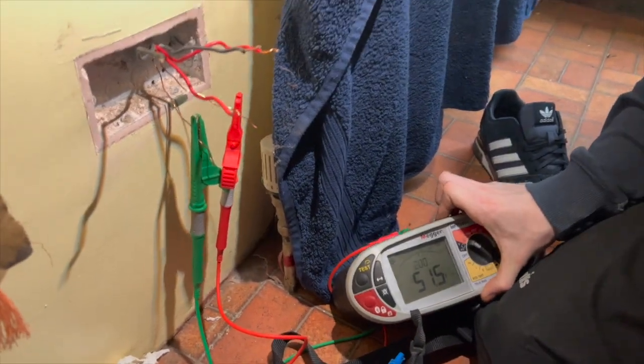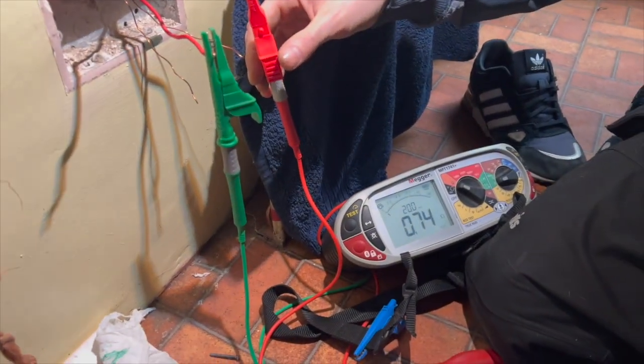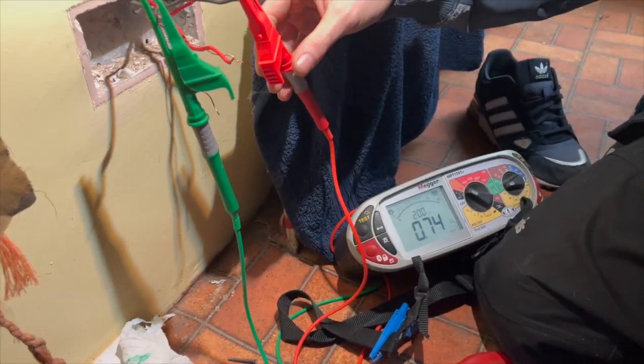Just testing this end-to-end - look, we found a load of the Verdigris, but lucky enough this is the bit where we've got to do a lot of the work, but there's no end-to-end readings - well, it's high. Just do the line conductors. About 0.74. Yeah, it's in the Verdigris. It's just cut the rooms and the kitchen, but this is all being knocked into one anyway, so it doesn't really matter.